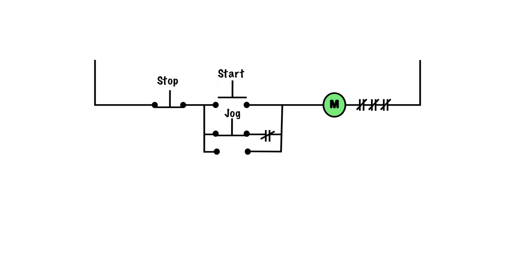Now we're going to press stop. We go ahead and press stop and that de-energizes the entire circuit. M coil de-energizes, M contacts open, and nothing works because power can't get through the stop. And power, also once the stop button is up, can't get through the start, can't get through the normally open contacts, and can't get through these normally open contacts.